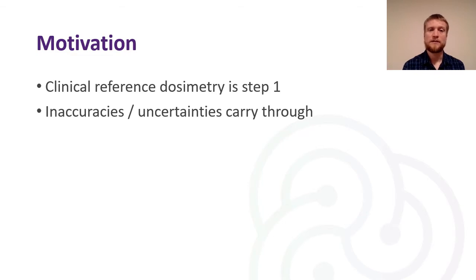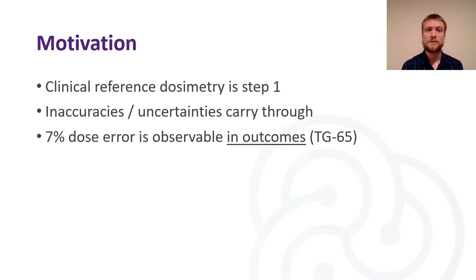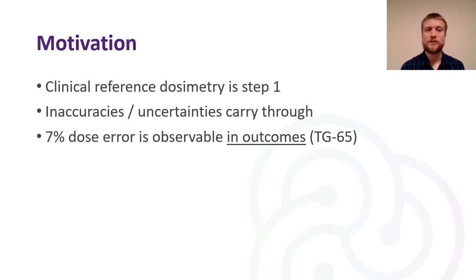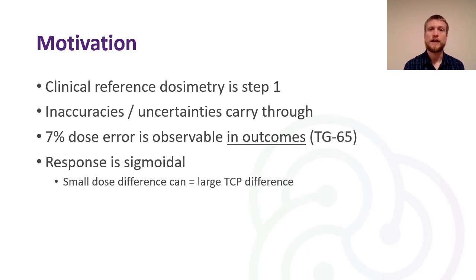We care about this because we want to target the therapeutic window where you have maximum tumour control while minimising adverse reactions in the patient. We also know that a seven percent dose error is observable in patient outcomes directly. This is the TG65 case study where there were 67 gynaecological patients receiving external beam photons of 25 MV energy, and many of these patients had adverse skin reactions and diarrhoea. The dose response is sigmoidal, so a small change in dose can cause a large change in tumour control probability or an increase in adverse effects. Of course this is site and stage dependent.